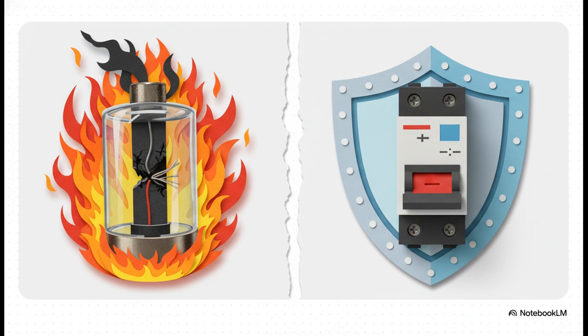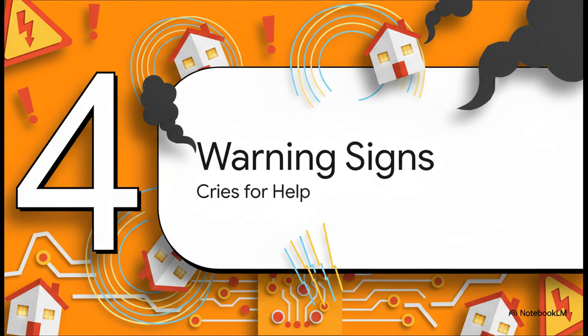But the real issue with fuses is a highly dangerous practice called overfusing. When a fuse keeps blowing, homeowners get frustrated, right? So they're often tempted to just screw in a higher rated fuse so it stops interrupting their power. No way. That completely bypasses the safety mechanism and turns your home's wiring into a direct fire hazard. That is exactly why fuse boxes are completely obsolete, not permitted in any new builds, and can even cause your insurance premiums to skyrocket. Which brings us to Section 4, warning signs and troubleshooting, cries for help.